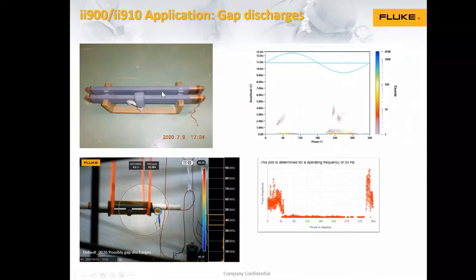The next example here. These are two parts, just models of a winding insulation. There's a conductor, copper conductor here, insulation, and on top of the insulation, some Corona protection material. The next one in parallel. And while energizing here, we see here a lot of Corona and possibly gap discharges.